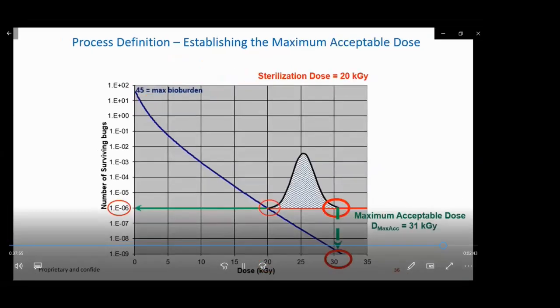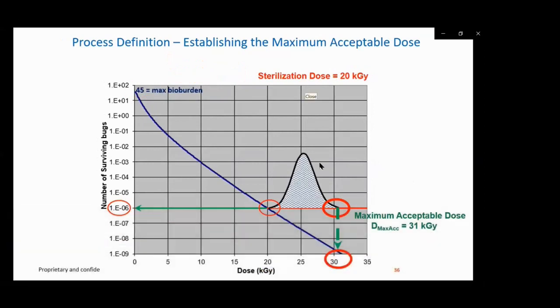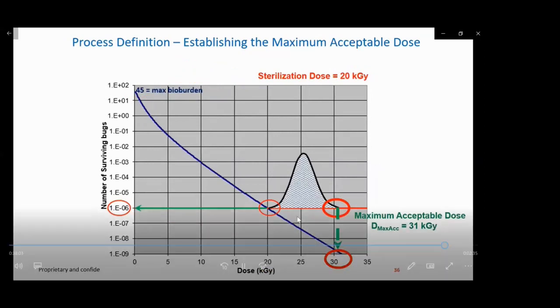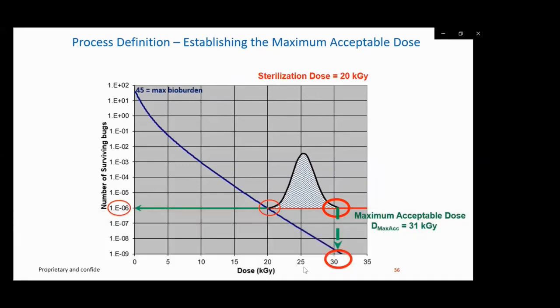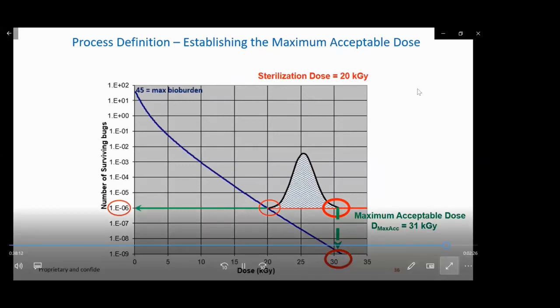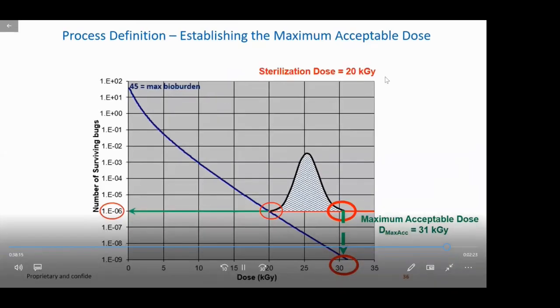This is what the process looks like, staying under a max acceptable dose of 31 kilogray and above the sterilization dose of 20 kilogray. This schematic doesn't picture the uncertainty, or the fact that we left room to get a dose augmentation of about 3 kilogray, but in general, that's the picture.